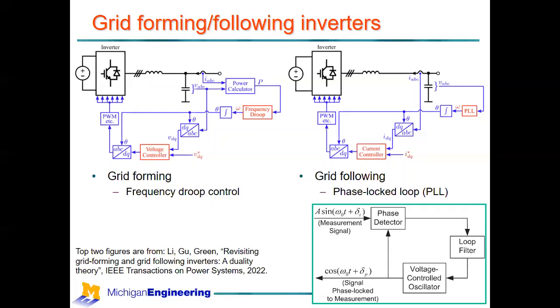One topic that is fundamentally important for decarbonising the grid is grid forming versus grid following inverters. When we think about solar photovoltaic, it produces electricity as DC, and that DC needs to be converted to AC. Inverters do that. For wind turbines, most are doubly fed induction generators, and the rest tend to be synchronous machines, but they all build on inverters to do some part of the conversion process to connect to the grid.